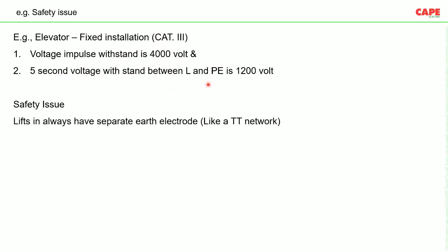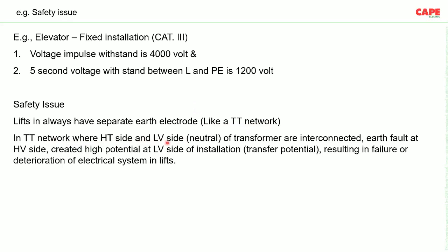Now the safety issue comes into the picture. All of you know that in almost all high-rise buildings, the lift has a separate earth electrode. Through the lift shaft, separate earth bus bars are running and connected to a separate earth electrode, and the network looks like a TT. Now, in a TT network, the power supply comes from a transformer, and the HT and LT sides are probably separate or probably interconnected. Now, if the HT and the LT are interconnected, an earth fault at the high voltage side creates high potential, please excuse the spelling mistake, at the LV side of the installation, a transfer potential, resulting in failure or deterioration of the electrical system in the lift.